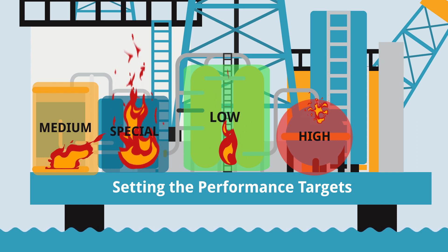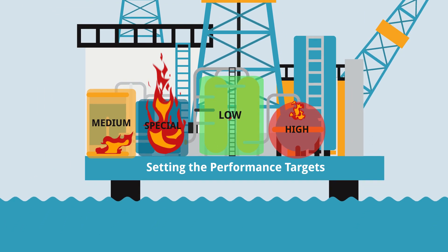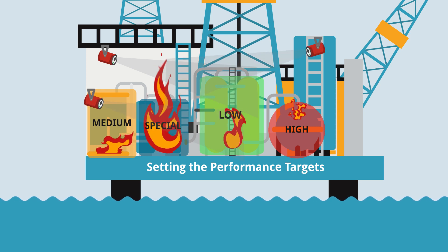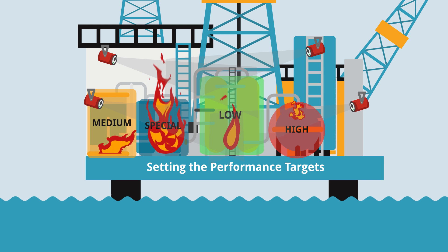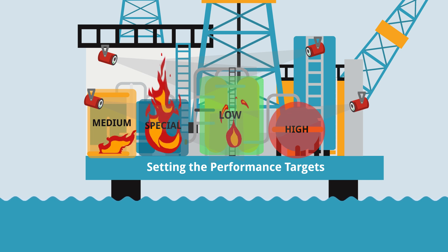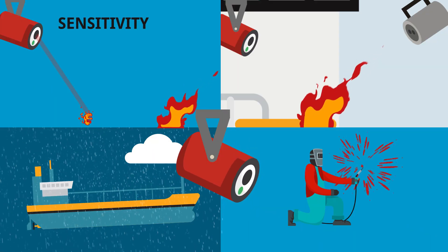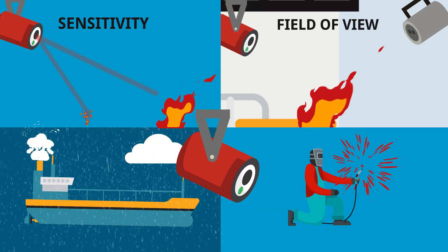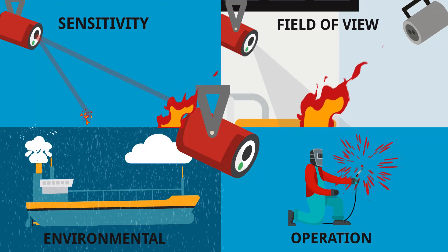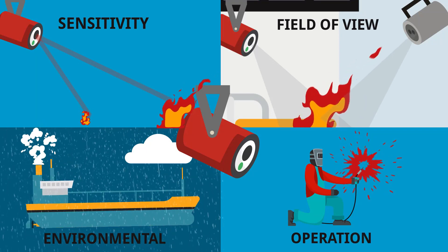Step 3: The designer then applies flame detectors in optimal positions considering the principle of operation, accessibility, and based on the unique characteristics of the flame detector being assessed. Parameters such as sensitivity, field of view, and robustness to environmental and operational conditions are key to developing a good design.